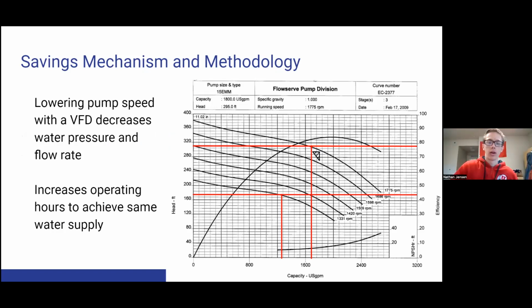Awesome. So as you can see here on this pump curve, this is just a dummy pump curve from a different assessment, but you can see that as you lower the speed of the motor, the RPM, it decreases both the flow rate and the pressure of the water, the head. So installing a VFD decreases both of those, which lowers the power usage. However, the drawback is that a VFD does consume some energy, and also you have to increase the operating hours to achieve the same water supply. But overall, installing a VFD is usually pretty effective at decreasing the energy usage of a pump.